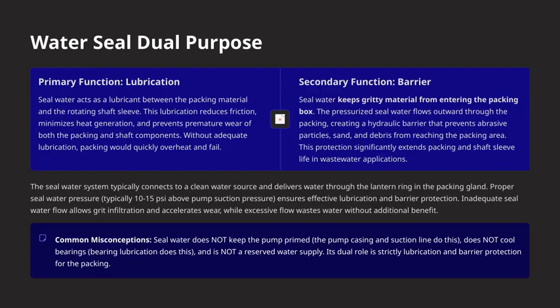It's also important to clear up some common misconceptions. Seal water does not keep the pump primed. That's the job of the casing and suction line. It does not cool the bearings. That's handled by specialized bearing lubrication systems. And it's certainly not a reserve water supply. Its roles are strictly to provide lubrication and create a barrier to protect the packing in demanding environments. Understanding these functions helps us appreciate how critical proper seal water management is for pump performance and longevity.